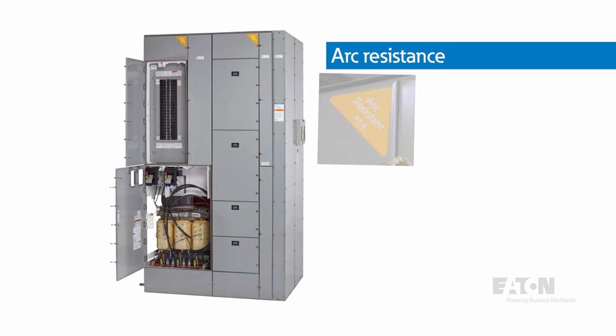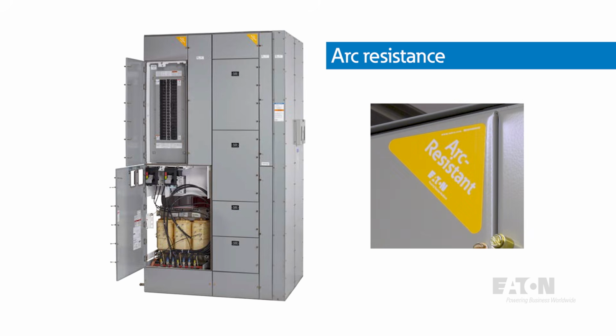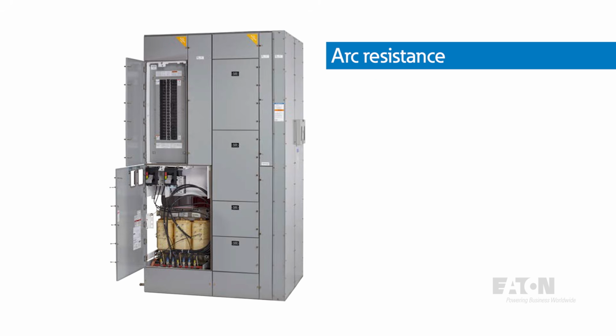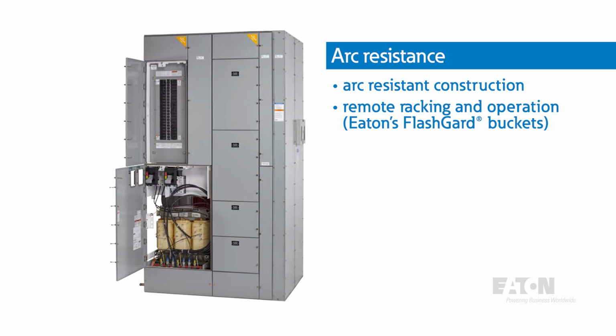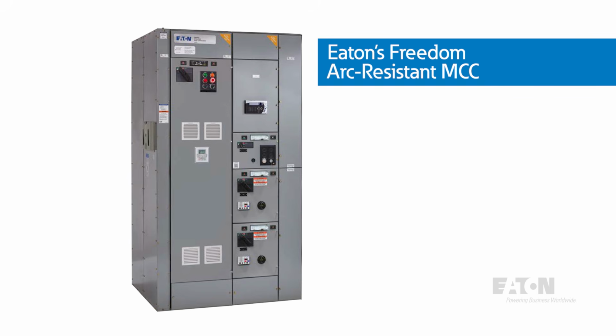There is generally a high risk of arc flash associated with MCCs since they are commonly hard to de-energize and often worked on while hot. Some special applications that add an extra level of safety to an MCC are arc-resistant construction and the ability for remote racking and operation with Eaton's FlashGard buckets. Eaton's Freedom arc-resistant MCCs are specifically designed to contain arc blast energy, enhancing workplace safety with an additional layer of protection. These MCCs are engineered with reinforced steel, latches, and hinges to provide containment of internal faults inside a space-effective package that has a Type 2 accessibility rating, ensuring arc resistance around the entire perimeter of the MCC.